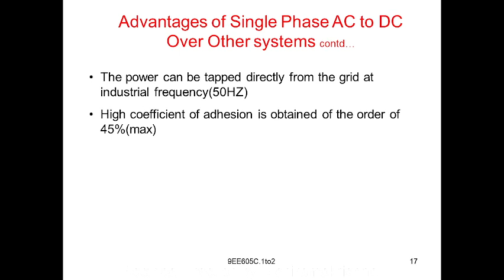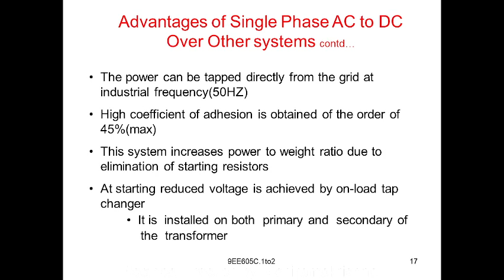In the DC system we use starting resistors, but in AC we are not using starting resistors. The reduced voltage at starting is achieved by using tap changers, which reduce the voltage at starting since high starting current is undesirable. This is installed on both primary and secondary of the transformer.